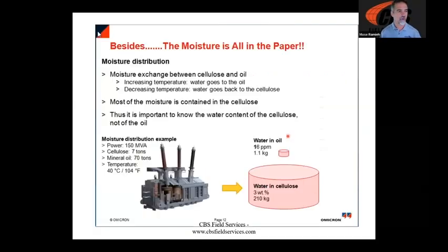Now, once again, I'm going to point out moisture in oil tends to be the small amount. The moisture tends to hide in the cellulose, in the paper of the transformer. And this picture does a great job of showing the proportions. So if you have an oil at 16 parts per million in oil, you might have 200 kilograms, I mean, just a lot inside the paper. So once again, keeping track of our moisture by doing some oil testing, which I mentioned earlier on.